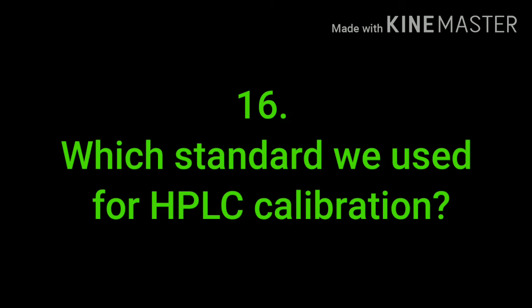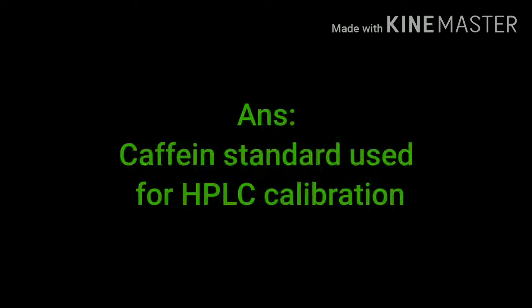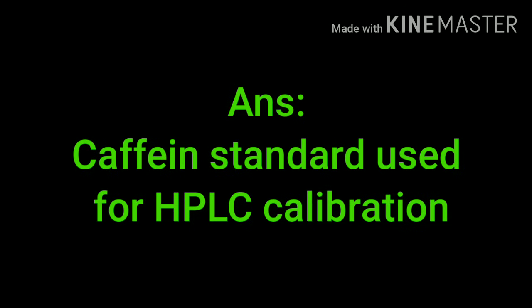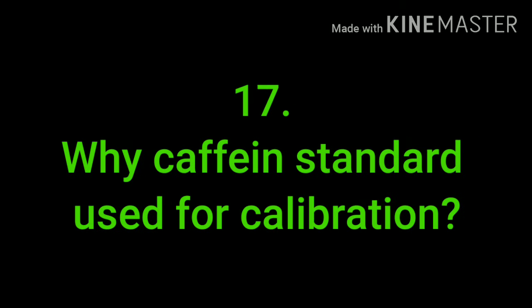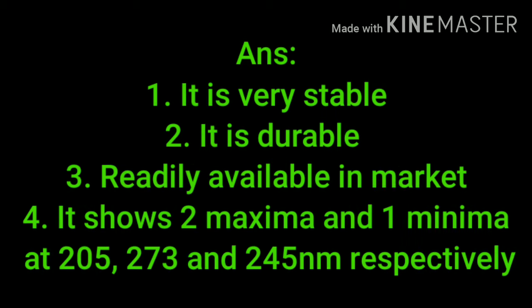Which standard do we use for HPLC calibration? Caffeine standard we use for HPLC calibration. Why caffeine standard? It is very stable, durable, readily available in the market, and it shows two maxima and one minima at 205, 273, and 245 nanometers respectively.